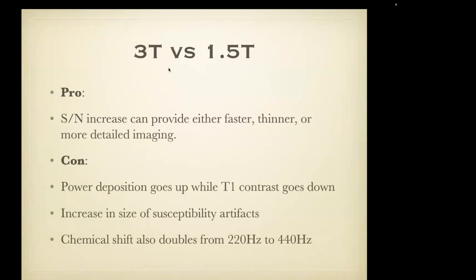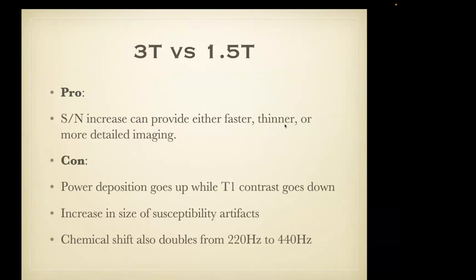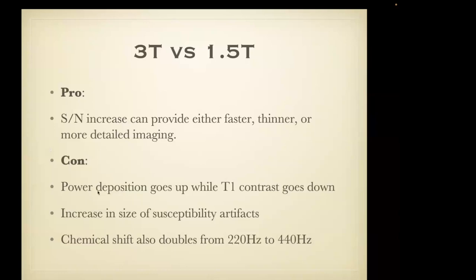Coming back to 3T versus 1.5T: the advantage is we can have either faster imaging, thinner slices, or more detailed imaging. In many sites in the United States where there's a premium placed on volume and throughput, many of the advantages of 3 Tesla have been dedicated to providing faster imaging. But the power deposition goes up, the size of susceptibility artifacts goes up, and chemical shift goes up.